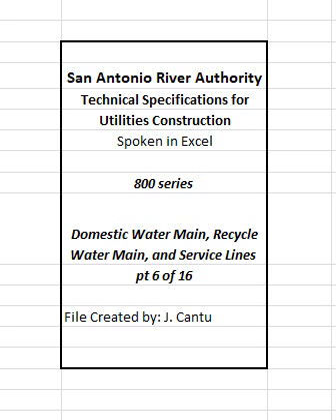The split band casting shall be designed to bottom out before clamping forces, 110 ft-lb minimum torque, can overstress the pipe, but will provide full non-directionally sensitive restraint at the rated pressure. Bolts and nuts used to attach the split retainer ring shall comply with ANSI B18.2.1 and SAE grade 5. Bolts, nuts, and restraining rods shall be fabricated from high-strength, low-alloy steel in accordance with AWWA C111. Restraint devices shall be Uniflange Blockbuster 1300-C or approved equal.